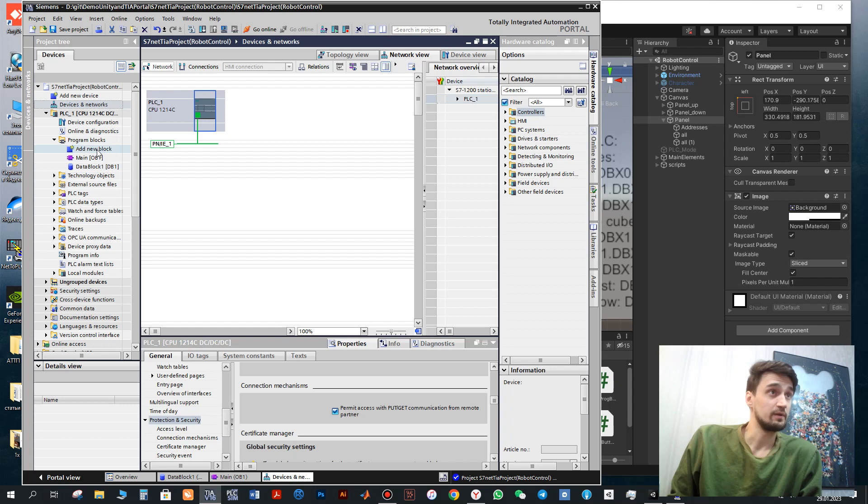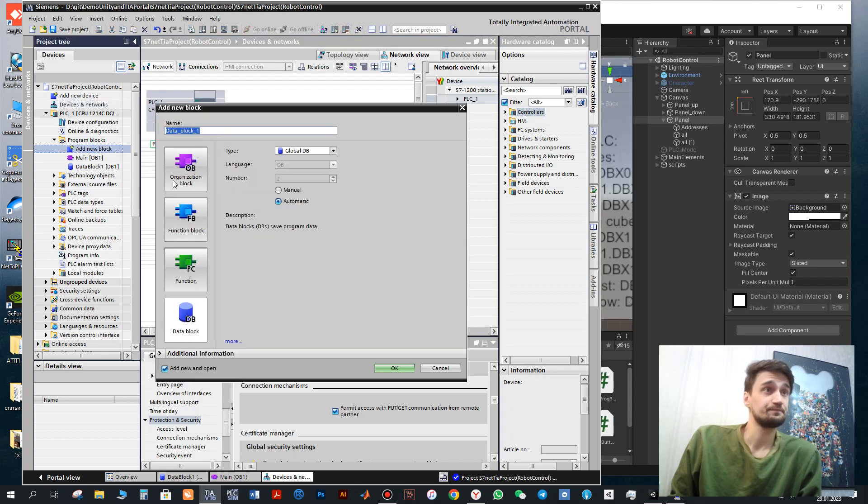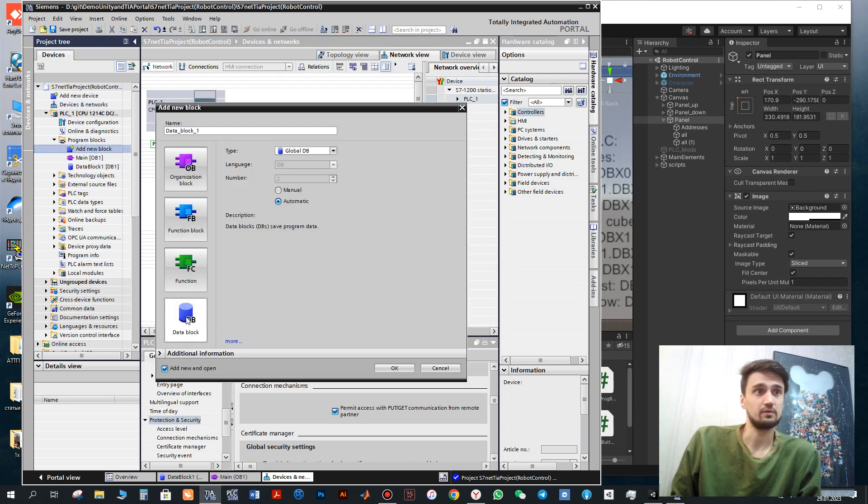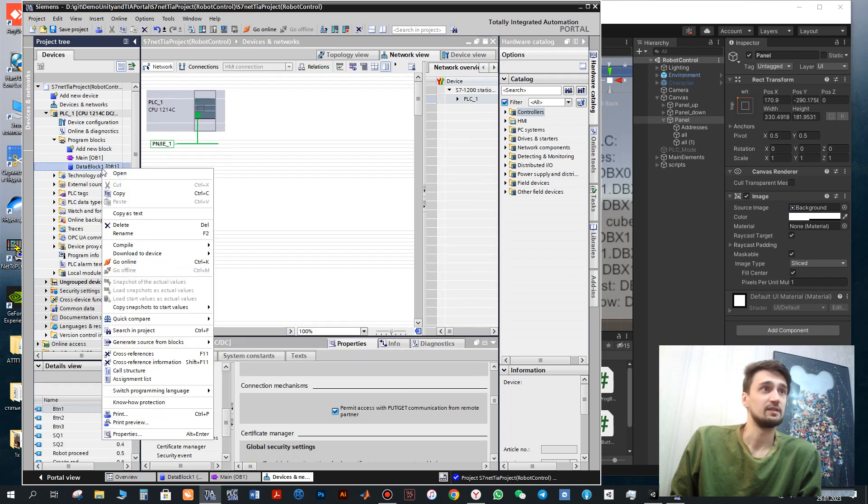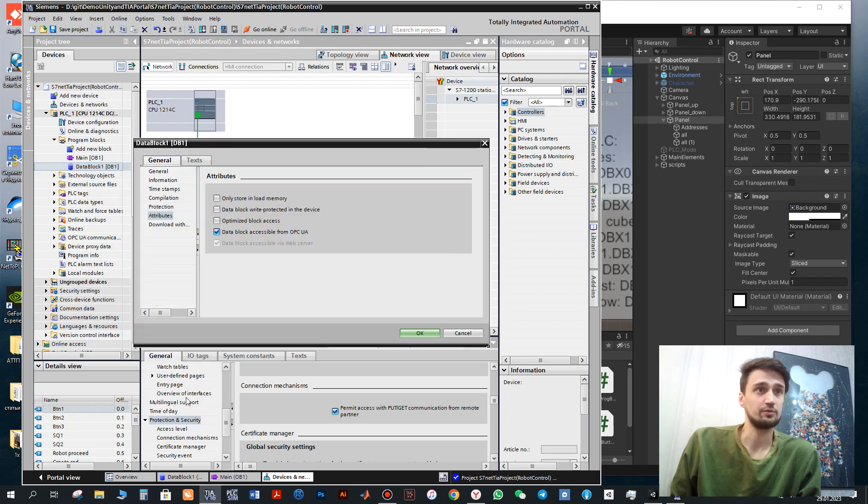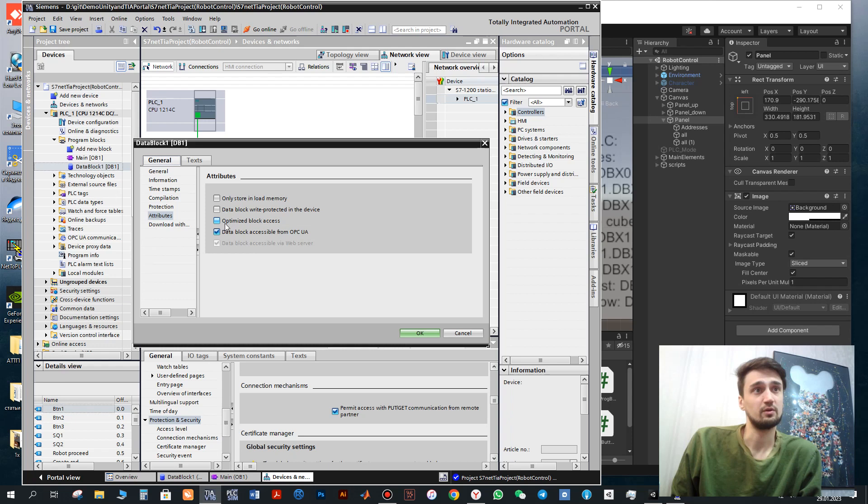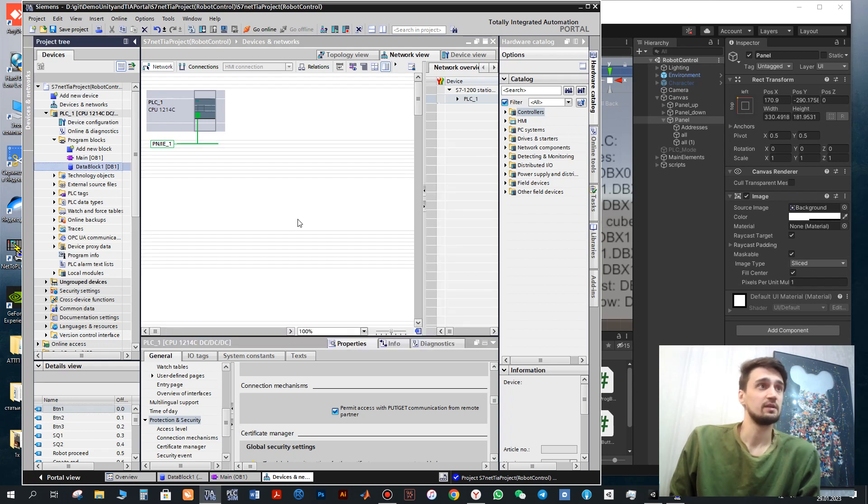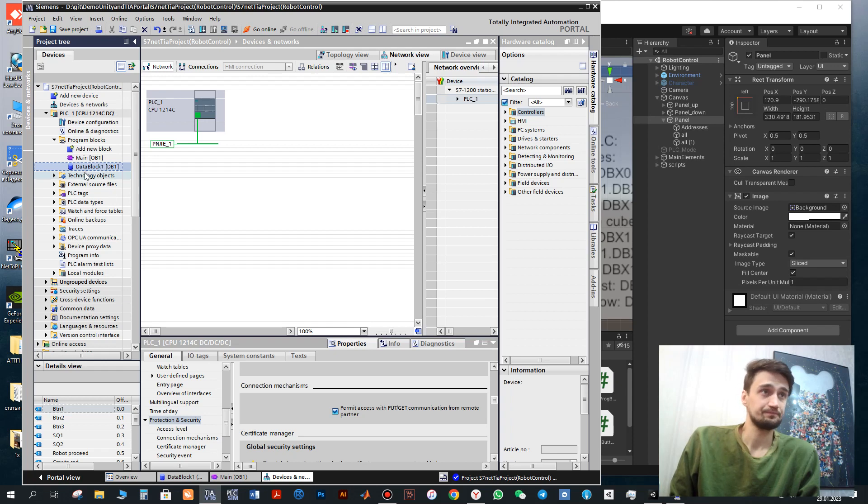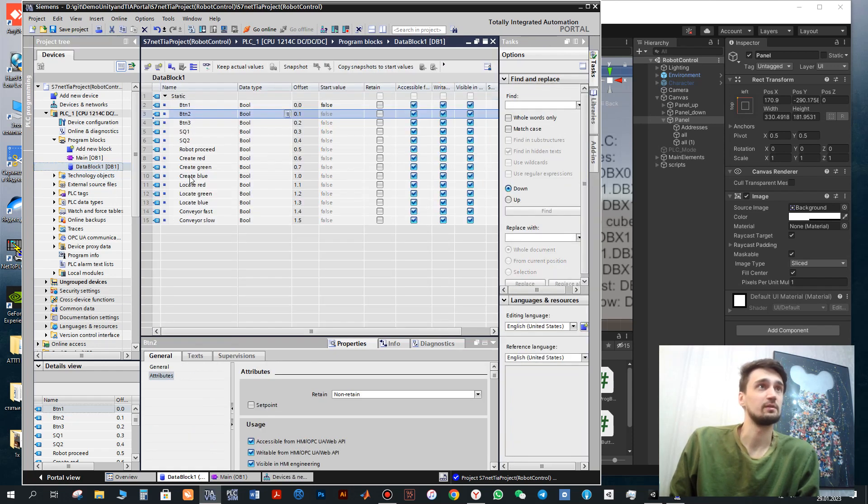Also when you create a new data block for addresses, so you click here and okay. Then you will have this data block for addresses. Here also you need to change properties. You need to click attributes, optimize block access, deactivate this toggle. Then you will be able to communicate between Unity and TIA Portal.